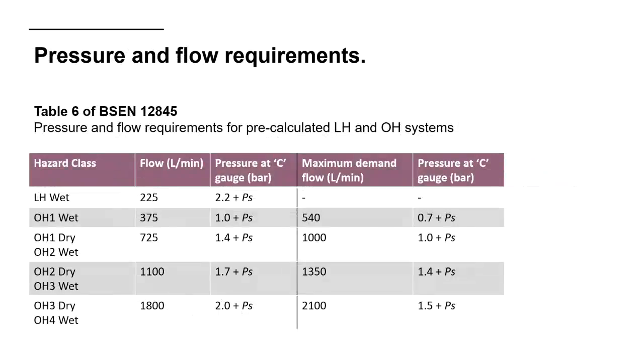Okay, so back to pressure and flow requirements. This is Table 6 from BS EN 12845, which is talking about pressure and flow requirements for pre-calculated light hazard and ordinary hazard systems. Your automatic fire sprinkler system might be pre-calculated, or it might be fully hydraulically calculated. Again, I've talked about that in the past. The point I want to make is that this table is for pre-calculated systems. If you've got fully hydraulically calculated, then the figures are going to be similar, in the same ballpark. So this is a useful table in terms of giving you an idea of what town main criteria you're looking for when you do your testing. This is showing you a flow at a pressure. We've got 2 points to look at, a nominal flow and a maximum flow, and both have a pressure associated with them.